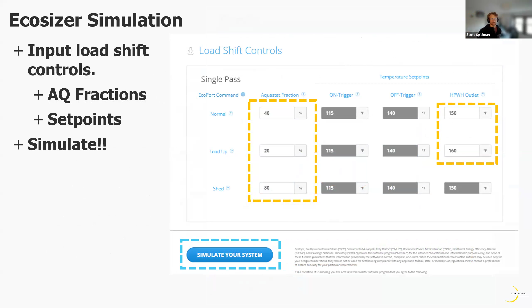And then in our shed, instead of referencing that 20% temperature sensor, we move that up to 80. And now this is just allowing our storage tank to drain more of the hot water out, and it allows us to ride through a longer period of time without needing to turn on the heat pumps or any other electric heating sources.